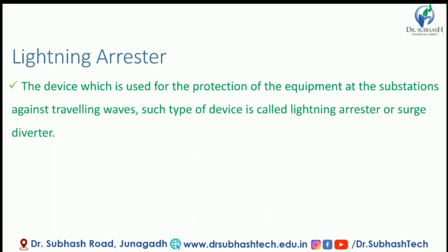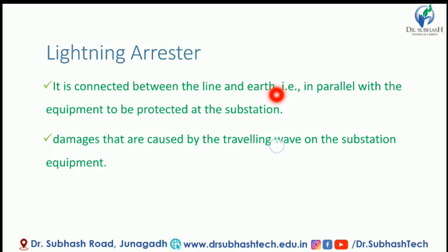When travelling waves are present, we use this equipment — the Surge Diverter and Lightning Arrestor. The Lightning Arrestor always diverts abnormal high voltage to the ground without affecting the continuity of supply. It is connected between the line and the earth, in parallel with the equipment to be protected at the substation.